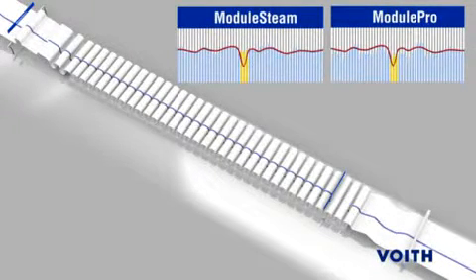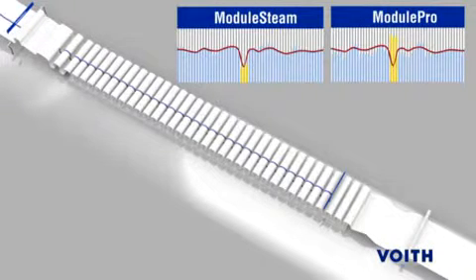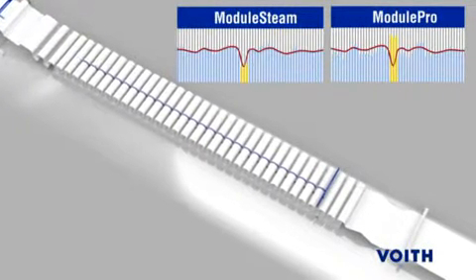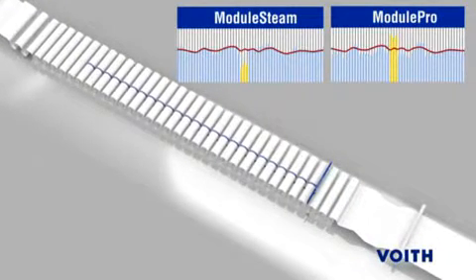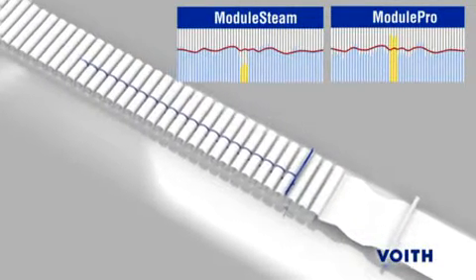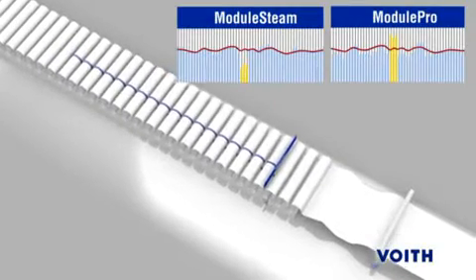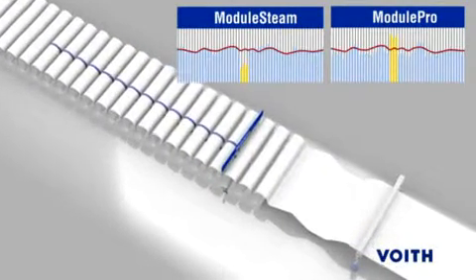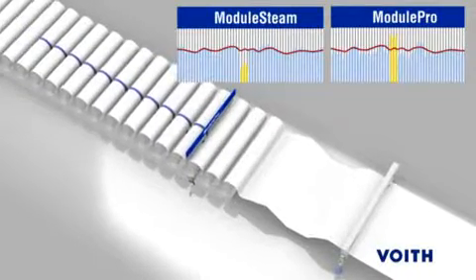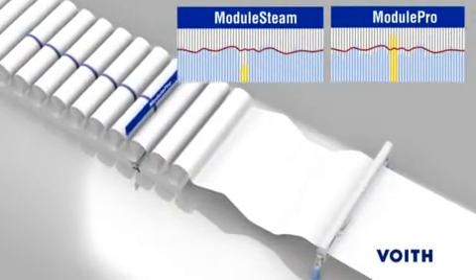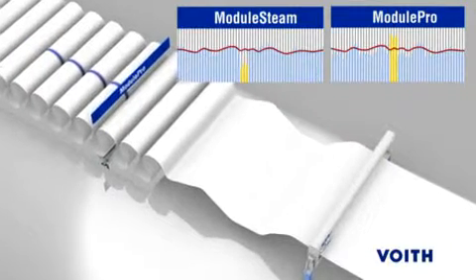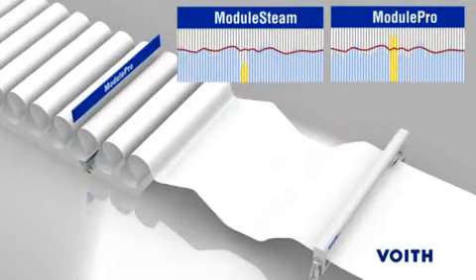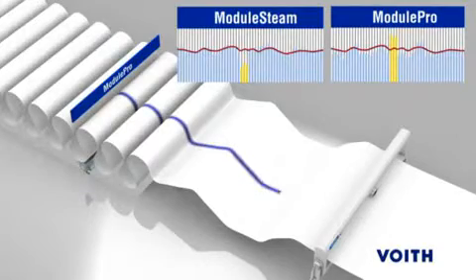Our example shows a deviation of the CD moisture profile at a given point on the paper web. OnQ Module Steam and OnQ Module Pro receive the same measurement value from the scanner and attempt to correct the moisture level, which here is too low. To do this, the OnQ Module Steam reduces the steam to dry less. Thus, the error is actually already corrected. However, the OnQ Module Pro does not know about this correction and increases the re-moisturizing. This overreaction produces a new error.